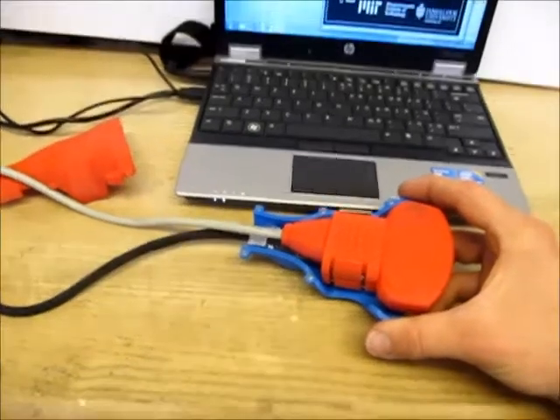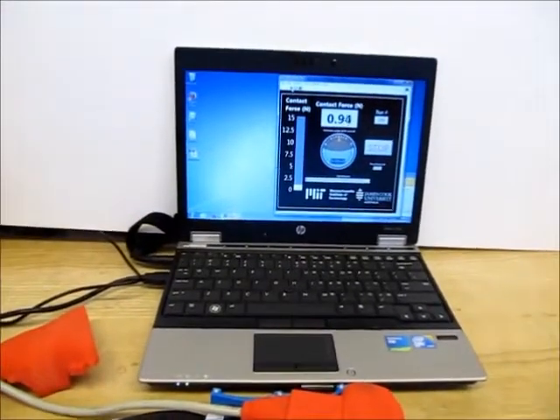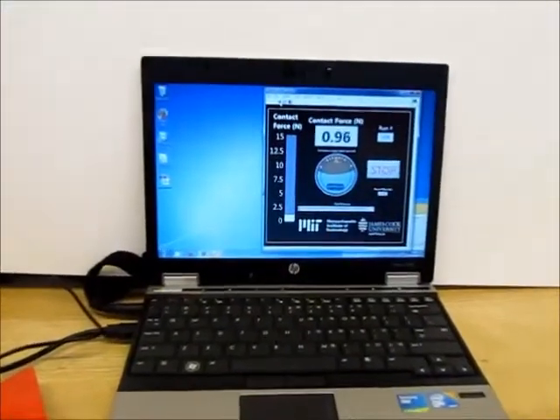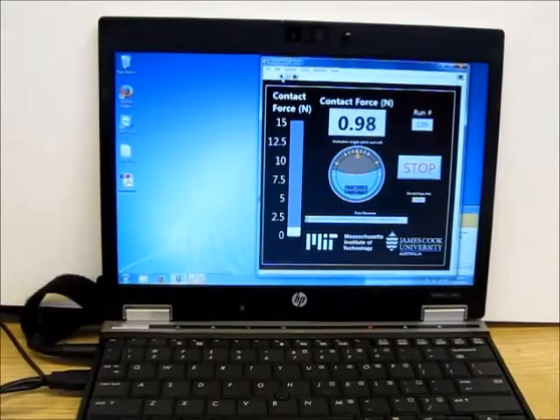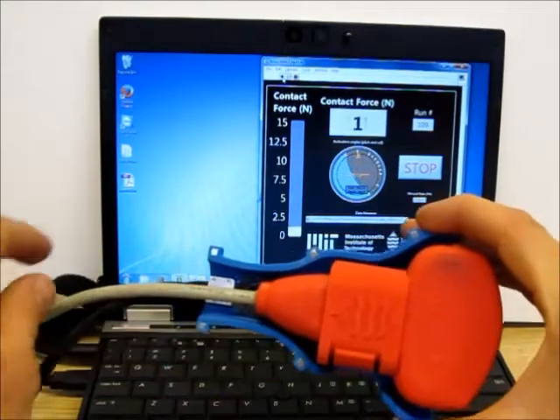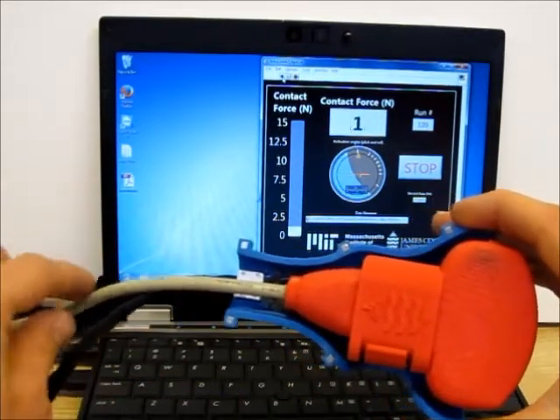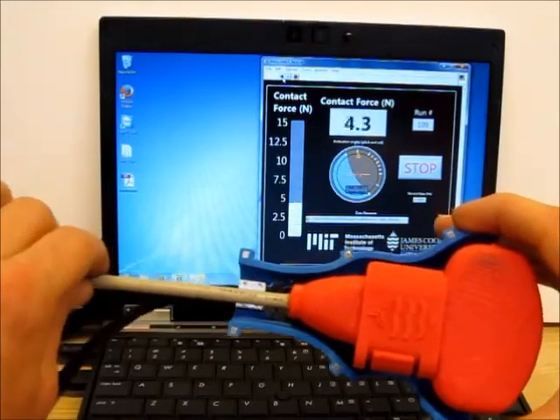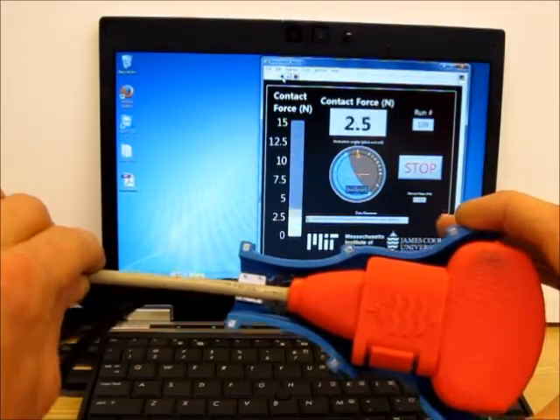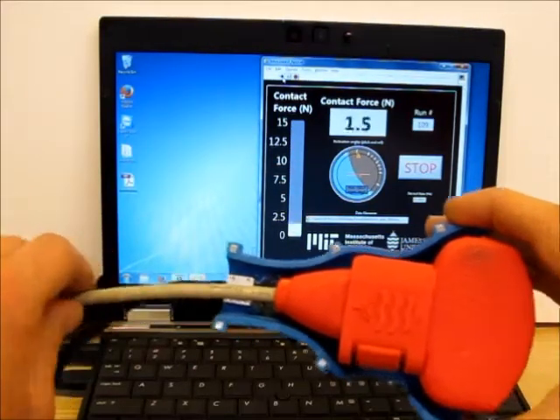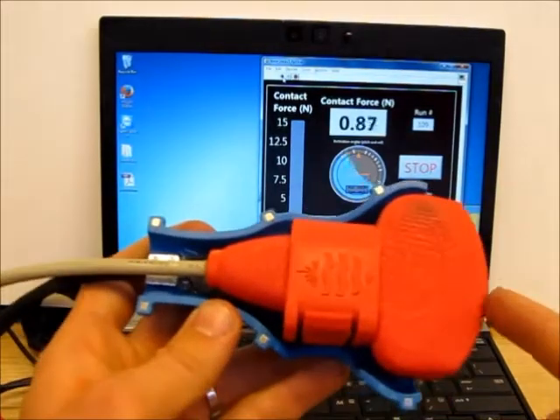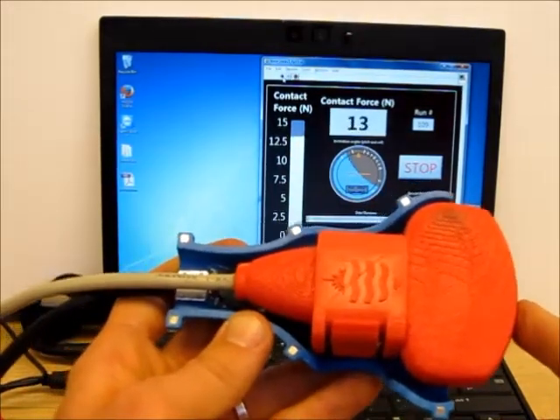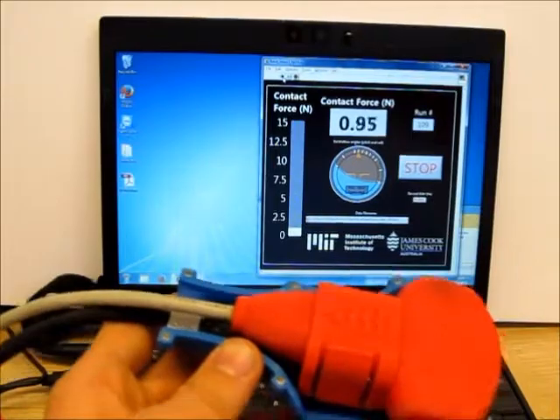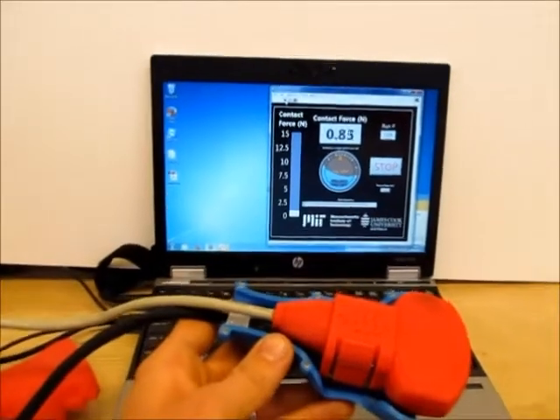So let's take a look here at the force gauge on the screen. Go ahead and zoom in here. So that's the current force reading. Now, in the current configuration, if we were to pull on the ultrasound cable, we see the force change. And we don't want that because we want to measure the force that's applied to the ultrasound probe face right here. So we need to do what's called strain relieving.